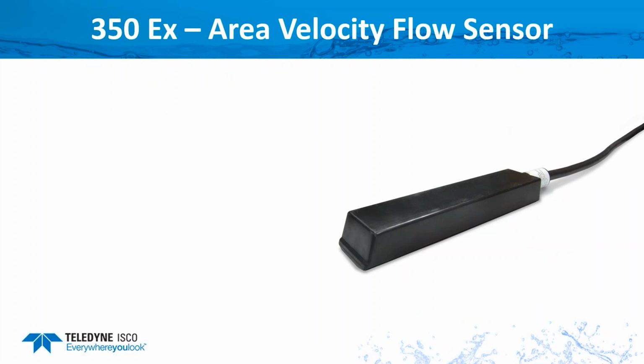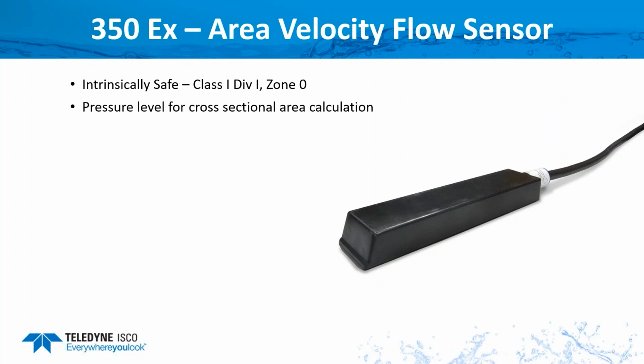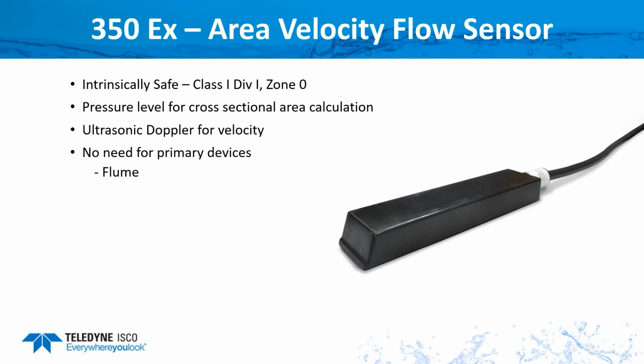Now the 350EX area velocity flow sensor is also intrinsic safe, class 1, div 1, zone 0 rated. This has a pressure transducer, and what that's going to be used for is to calculate the wetted cross-sectional area in your channel or pipe. It uses the ultrasonic Doppler for the velocity, and the good thing is there's no need for a primary device. You don't need the expensive flume or weir to install. You can install an area velocity sensor in most any open channel, round pipe, rectangular channel, oval, whatever it is, to calculate your flow.